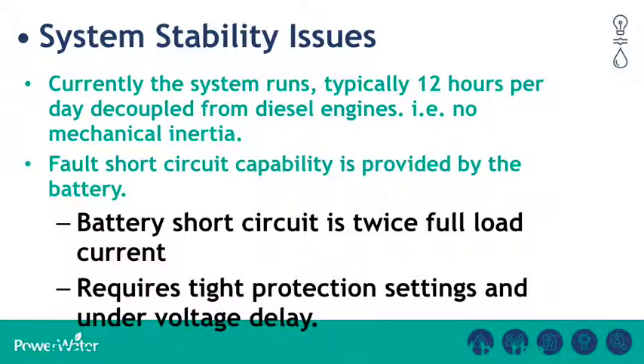The nice thing about an inverter grid system is that it's rock solid 50 hertz. We can do 100% load acceptance, which diesel generators struggle with. It's highly stable - we've swung from charging to discharging within milliseconds, and the system stays super stable.